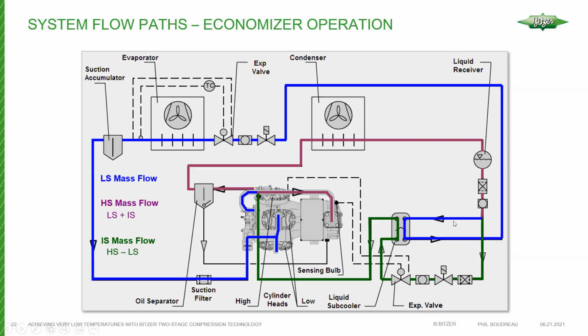Okay, so we're subcooling the refrigerant, and then that's our main liquid line, is what you see in blue. Okay, up to the expansion valve, and then through the evaporator, where after the refrigerant's expanded, we absorb the heat, and then we superheat to protect the compressor. You're generally going to have an accumulator on a compressor.